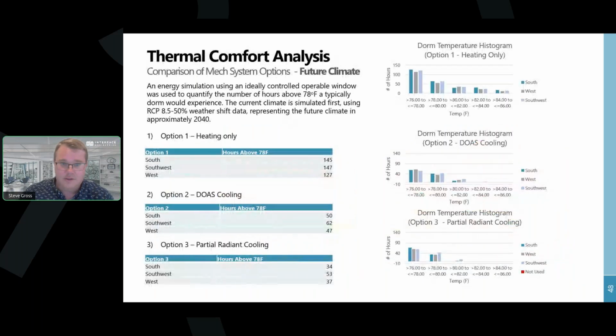On the next chart, we're showing a similar level of data, looking at how impactful the future climate is against the strategies we considered. Charts on the left are the summary number of hours per year above 78. Charts on the right are histograms binning the temperature data for 3 different orientations. We're trying to zero in on where to target impacts, insulation levels, and shading, as well as whether we could get away with a partial cooling approach on only one side of the building, avoiding it on, say, the north side, to save money.